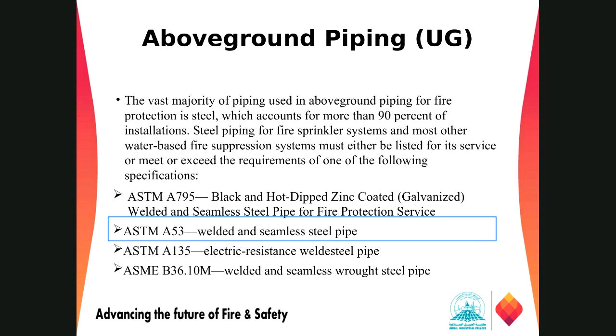NFPA 13 provides the wall thickness, right? What should be the thickness of the pipe? We call it the schedule: schedule 10, schedule 20, schedule 40. Schedule 40 is the most common one, which is more than enough for a pressure of 175 psi. When we are talking about the schedule, we are talking about the thickness.